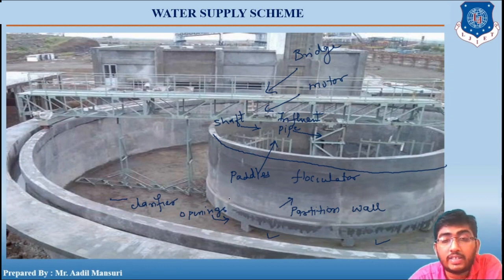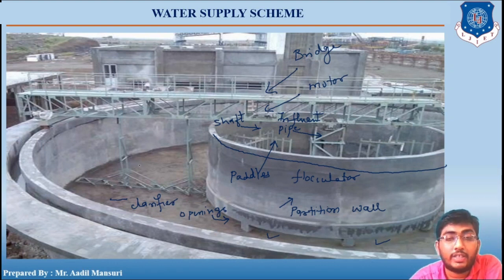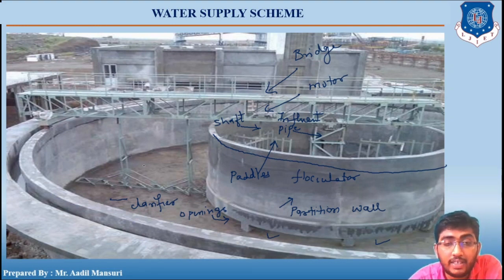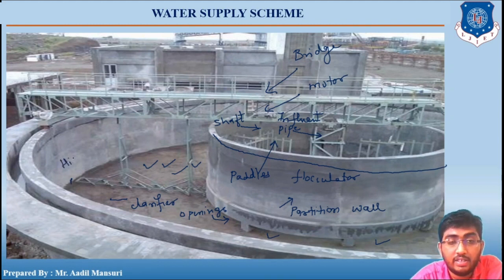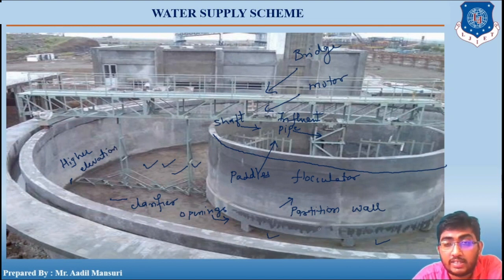The flocs being used in the flocculator will settle after capturing the suspended solids, and these flocs will settle at the bottom of the clarifier. There is a slope at the bottom of the clarifier - the outer portion is at a higher elevation and the center portion is at a lower elevation.